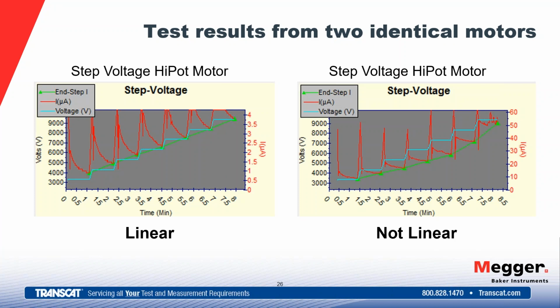So good insulation systems behave that way. We see here this line that we've drawn through the end step values represents a constant resistance no matter our voltage. So whether we're down here at 400 volts or 3,200 volts, or whether we're up here at 9,300, our resistance would stay the same. Our insulation is good. That's the indication of good insulation.